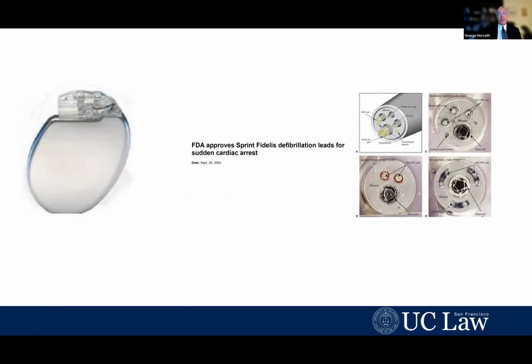Unfortunately, just 3 years after the device had been approved by the FDA, the manufacturer initiated a series of corrective actions that the FDA soon labeled as a Class 1 recall, which is a label that the FDA applies when there's a problem with the device that causes a reasonable probability of serious adverse health consequences or death. And this was done because these leads were failing much, much more frequently than other leads. And when the lead failed, it would be unable to deliver a life-saving shock when needed. And sometimes it would actually cause the defibrillator to deliver hundreds of shocks when they weren't needed.